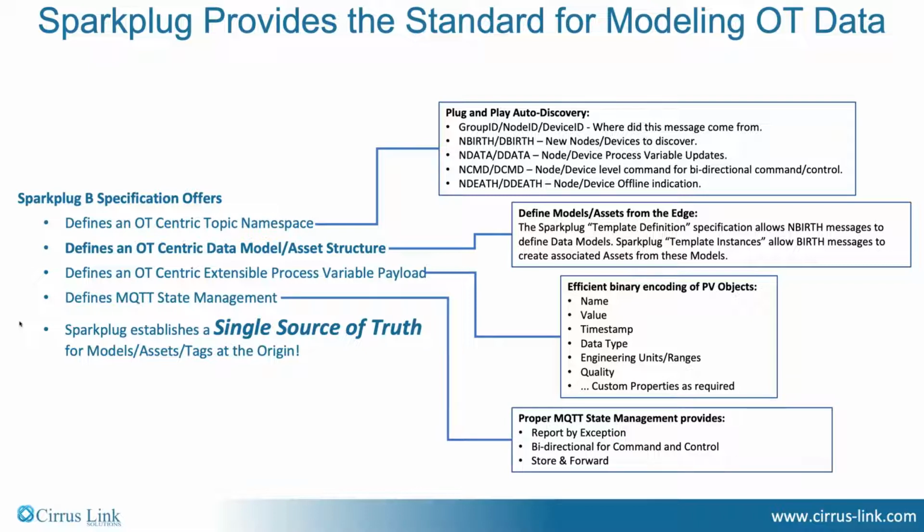One thing that's been very interesting is that in 2015, we introduced MQTT Engine. And people were saying, hey, when the network goes out, we're still getting gaps in our data and gaps in our trends. So we figured out that I know the state of my MQTT session, and I've got an object containing my measurement, so I can put those in a store and forward queue with the timestamp. Now when my MQTT network comes back online, I can publish all of those tags that we would have lost in any other methodology.